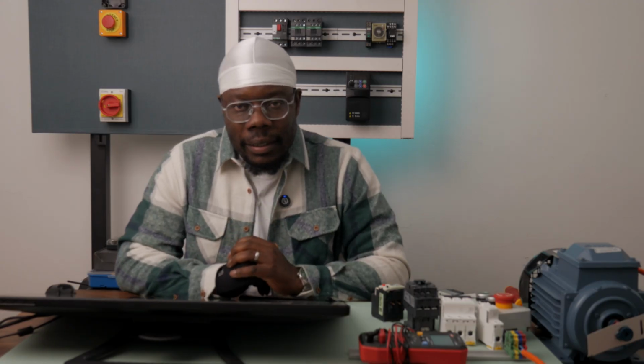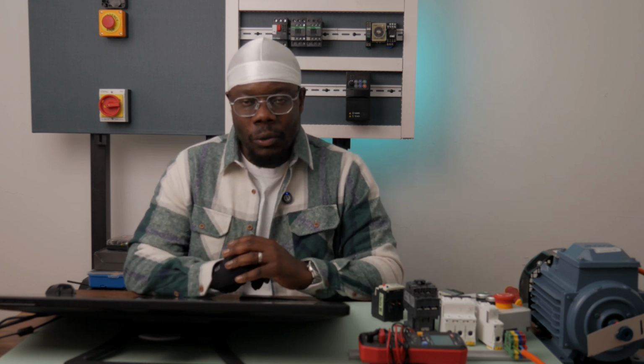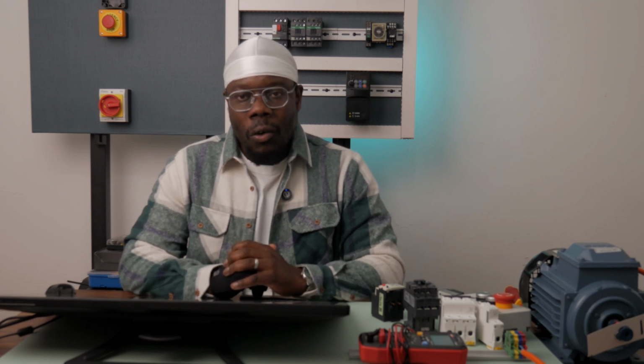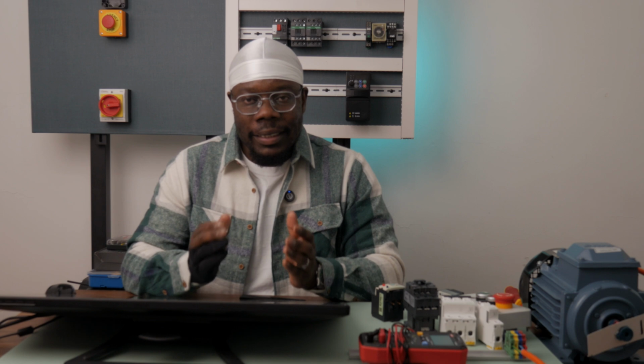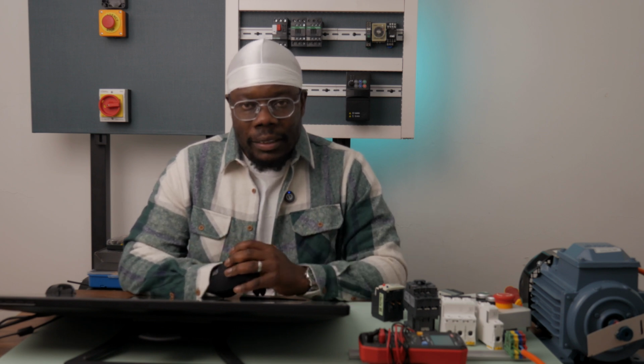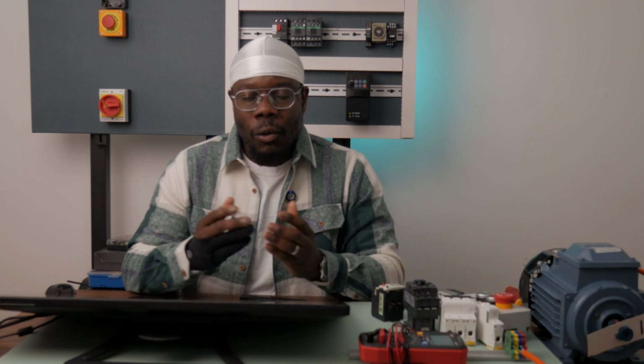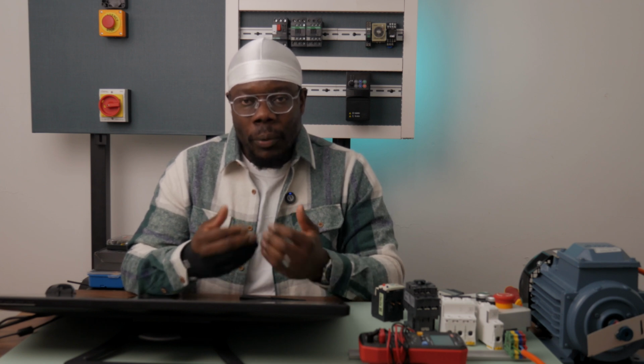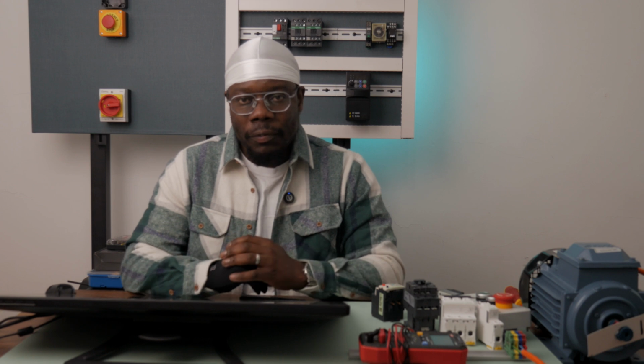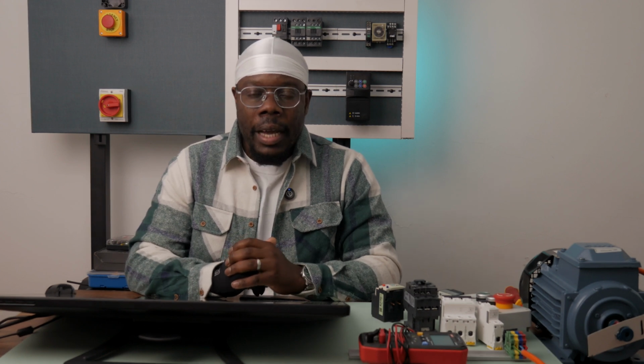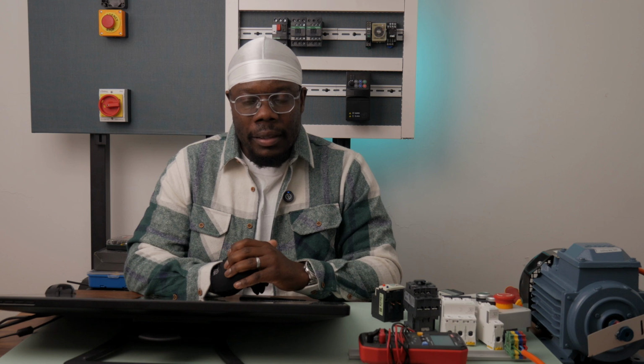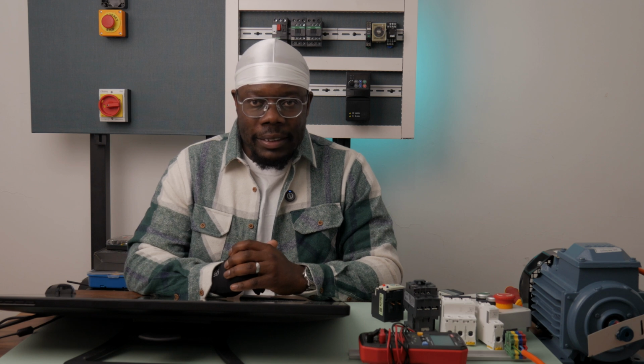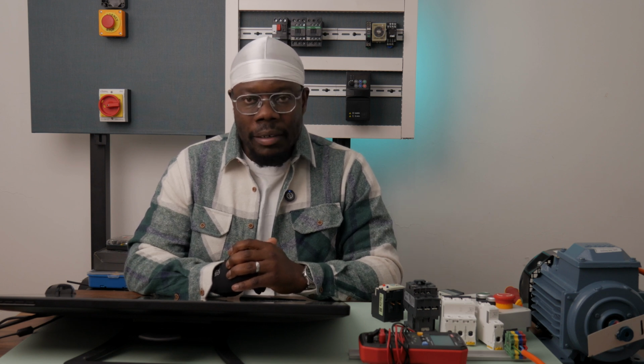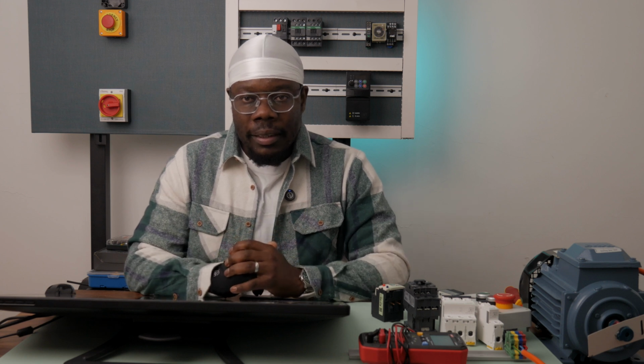Now let's quickly discuss the fail-safe mechanism of a simple direct online starter circuit. If this circuit is stopped by an overload or by an emergency stop, it will not restart itself even after the emergency stop button is reset, or even after the overload is reset. So this is an important safety mechanism for this type of direct online starter circuit. Now, before we draw and wire up the direct online control and power circuits, let's quickly go over the advantages and disadvantages of direct online motor starters. So we're going to start with the advantages.